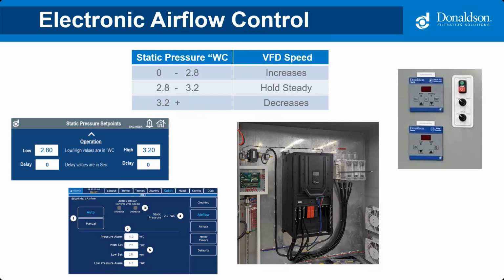Depending on the type of equipment in the control panel, the controller may send an analog speed reference to the variable frequency drive, or it could also send a digital signal to increase the speed and a separate digital signal to decrease the speed. So there's quite a few ways to go about this. The drive you see in black is a fairly large example. VFDs for these applications could be as small as 1 horsepower or as large as 600 horsepower. And very common sizes that we see are 10 horse, 30, 50, 75, 100, 150 like the one shown here, and 200 is also pretty common.